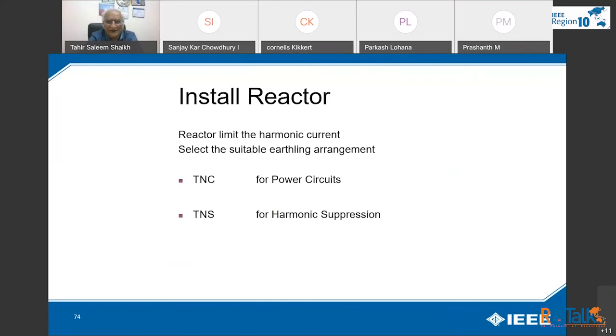And apart from that, going further, TN-S will have a separate earthing circuit and TN-C will have a combined one. For the power circuit, TN-C is normally recommended, and TN-S is recommended for harmonic suppression. For critical loads, IT is recommended, where the neutral is not earthed. In IT, a single fault will not trip your circuit breaker, and when a second fault occurs, a double fault, the breaker will trip. So there are certain limitations. You should have a good grounding for the surge protector as well as for harmonic distortion limitation.